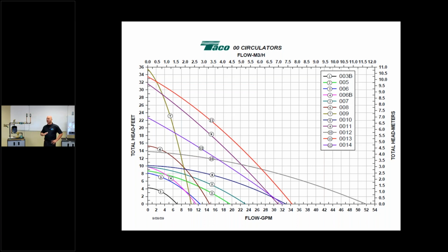But because of load shifting, because of zone valves opening and closing at different times, all the different apartments using different temperatures or whatever, the little circulators will overcome. Will it work? Is it working? Yes. Take it out and redo it? No, we're not saying that. But we're saying if you have a problem, we want you to understand how to get to the root cause of that problem. So he may have zero problems, but if he had a system installed properly, he might take his energy cost down dramatically.